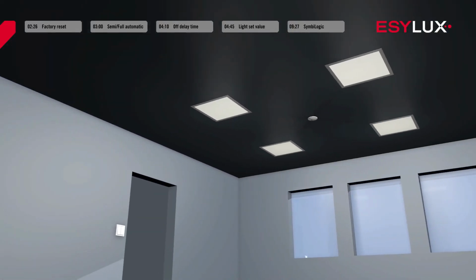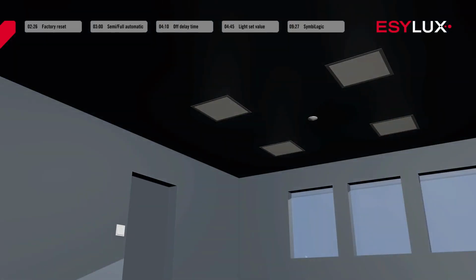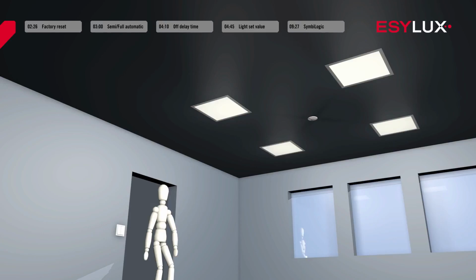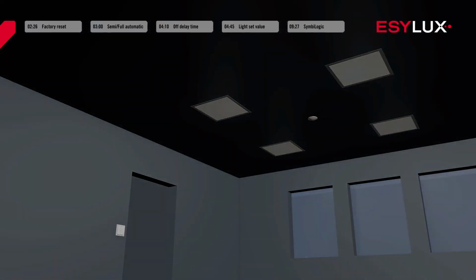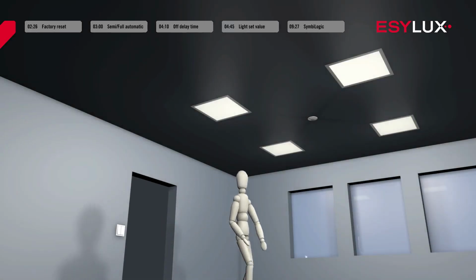In semi-automatic mode, the light only turns on when the button is pressed. In fully automatic mode, the light also switches on if the presence detector has detected a movement and the ambient light is below the preset light target value. The process for setting the light target value will be explained later.